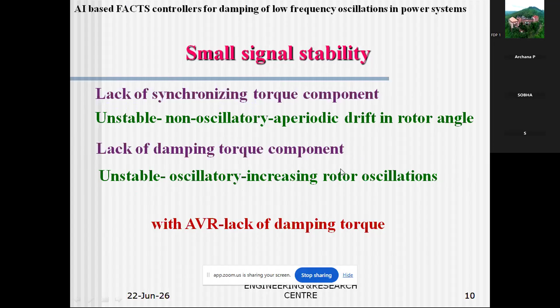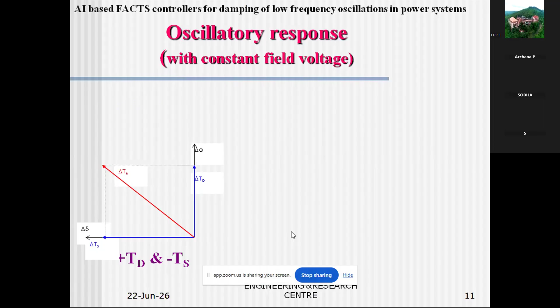If there is no AVR, the system is likely to have a negative synchronizing torque. See, this is negative and damping torque is positive because there is no AVR involved. That is, the field is kept constant. Under that condition, this is the total electrical delta TE, which is the summation of delta TD and delta TS. However, TS is negative over here. So the system is going to drift like this. This is called non-oscillatory instability: a steady increase in the rotor angle, delta delta, with respect to time, due to lack of sufficient synchronizing torque.